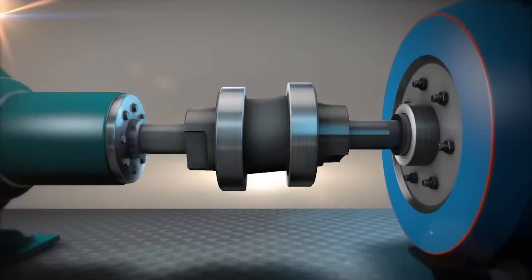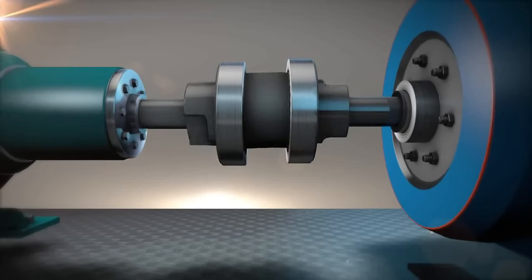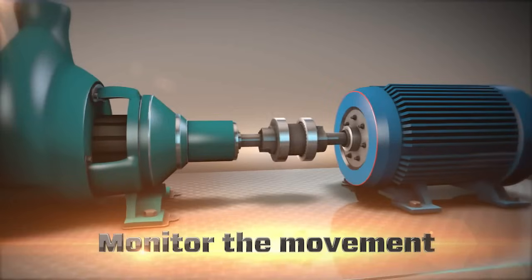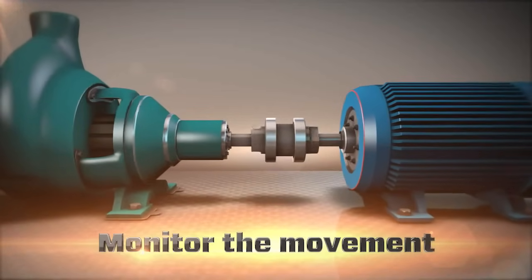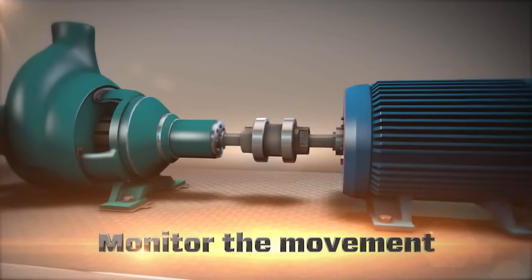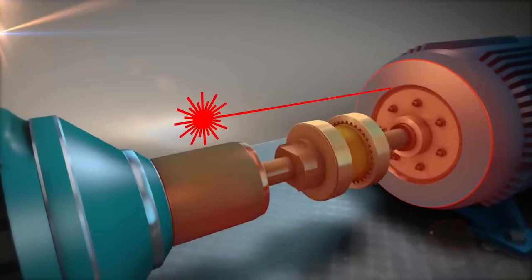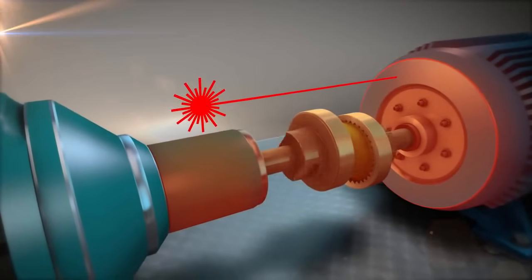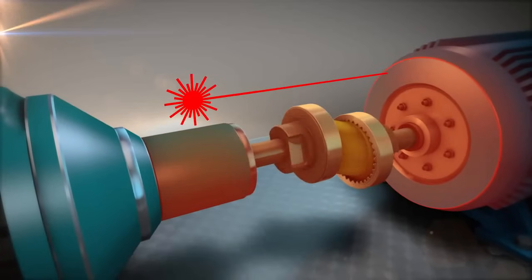To do this, we need to determine the amount of movement that occurs between the two shaft center lines. The best of several ways to determine this information is to monitor the movement. We track the positional change of the machines continuously from the cold to the hot condition, or vice versa.